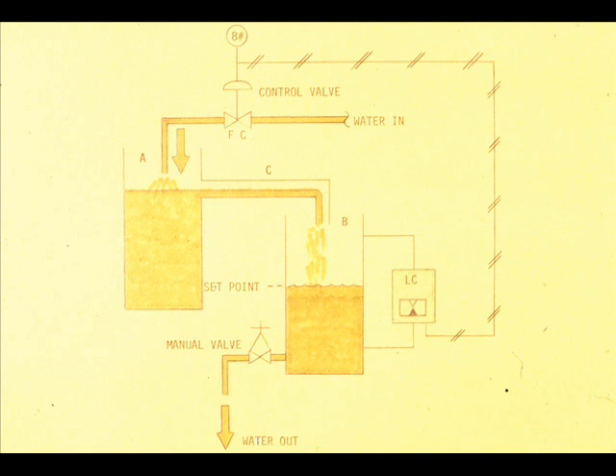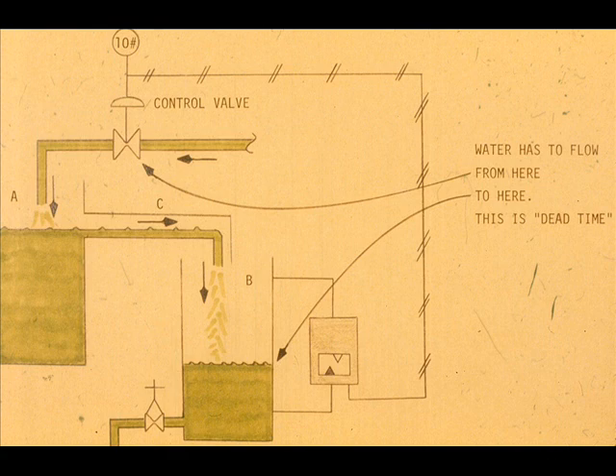Let's rearrange our level control schematic so our level control is admitting water to tank A. It gravitates to tank B, and we manually set the rate of withdrawal from tank B. Now we will slightly open the manual valve. The level slowly falls in B. The controller opens the control valve and admits more water to A. Does this immediately affect the level in B? No, because the water has to flow from the control valve to tank A, raise the level in tank A, and then flow through flume C to tank B before it has any effect on the level in tank B. This is known as dead time.